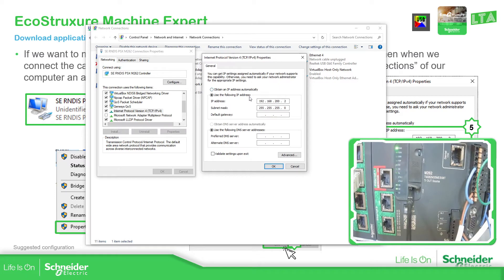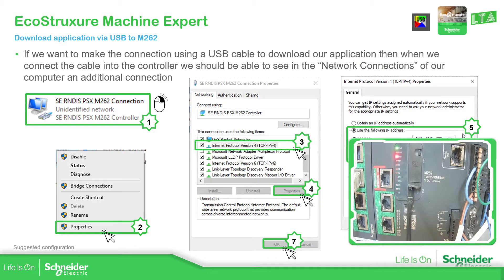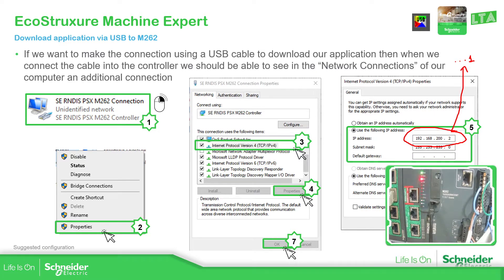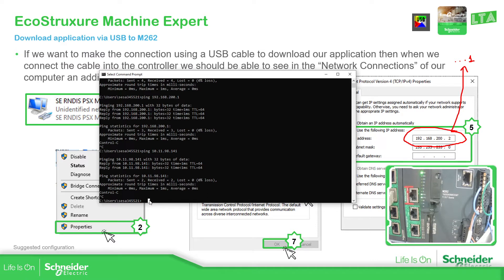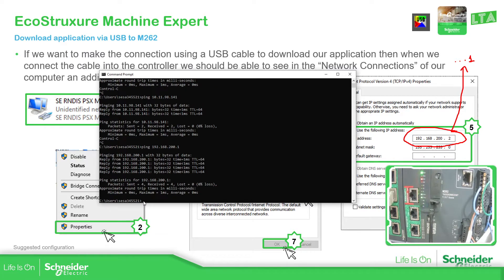This will allow us to connect with the controller in our software. One important thing: if you are using this communication, it means that the computer on the other side would have an IP address. On the M262 it will be the same, but with the number one at the end. If we are connected with this, we should be able to ping the IP address — ping 192.168.200.1. You can see there is some ping and there is some answer from the PLC.